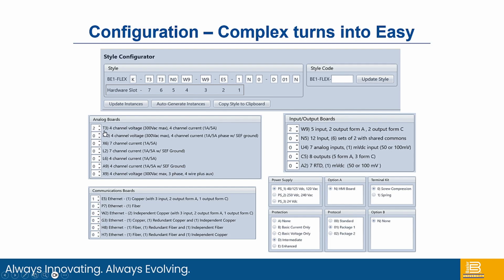In this particular example, I have 2 of the T3 boards, which brings in 8 channels of voltage, that's 4 times 2, and the same is 4 times 2 is 8 channels of current. On the communication board, we're using the E5, which provides a copper Ethernet port plus some contact I/O, and you have other boards available if you wish.